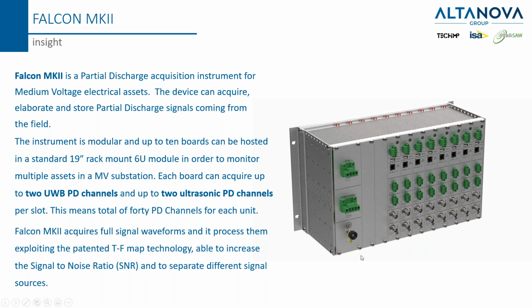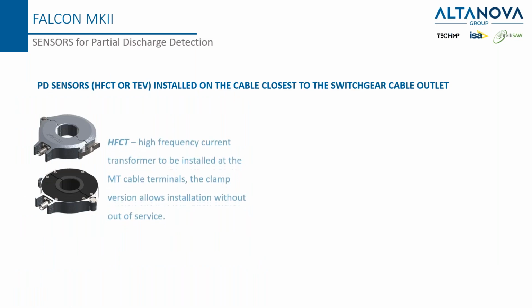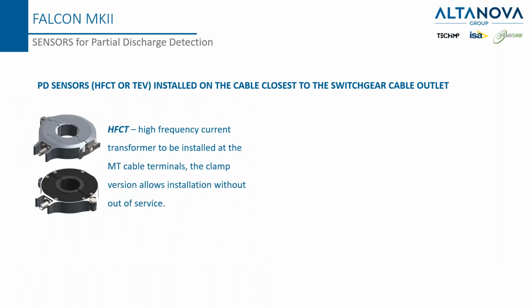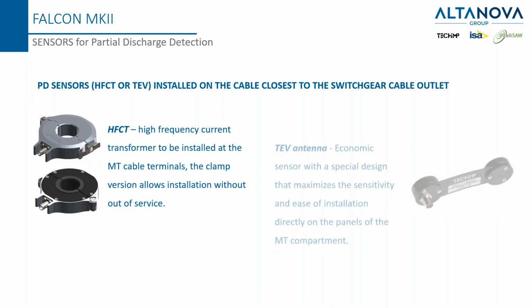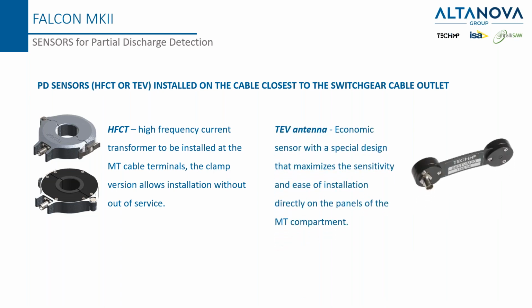This unit, the Falcon Mark II, acquires a full signal waveform and processes it exploiting the patented TF map technology, able to increase the signal to noise ratio and separate different signal sources. Also here, the main sensors used are HFCT installed on the cable closest to the switchgear cable out. For the TEV, that is the sensor with a special design to maximize the sensitivity and ease of installation directly on the panels of the medium voltage compartment.